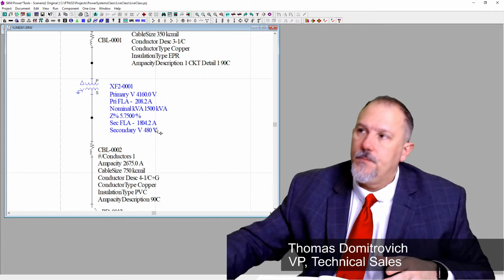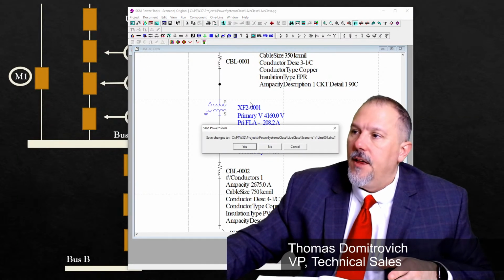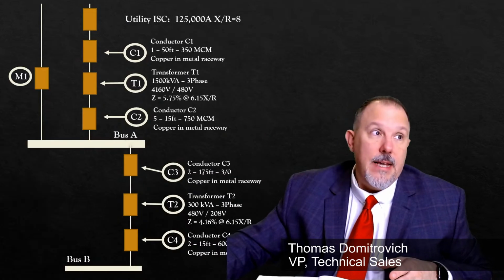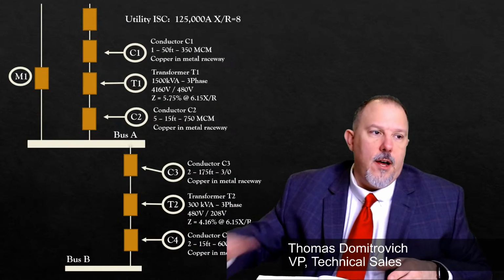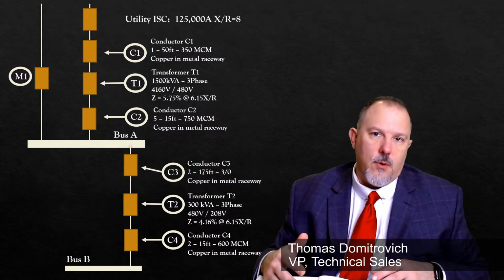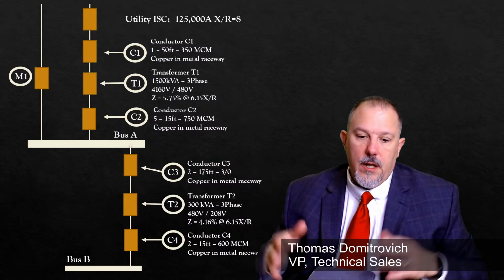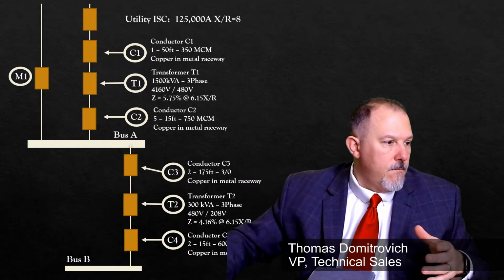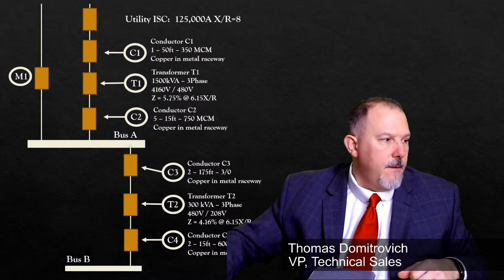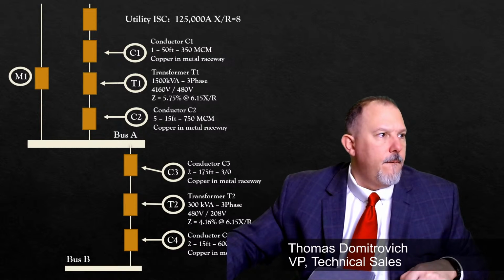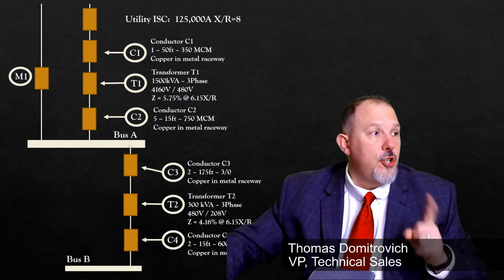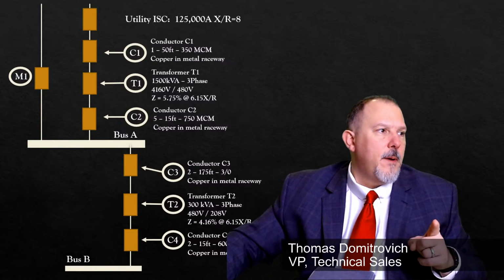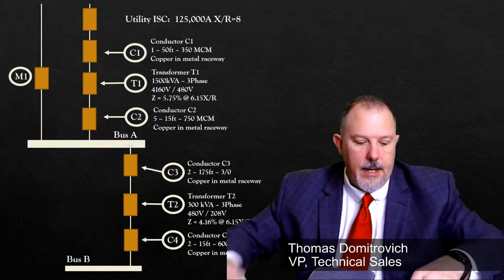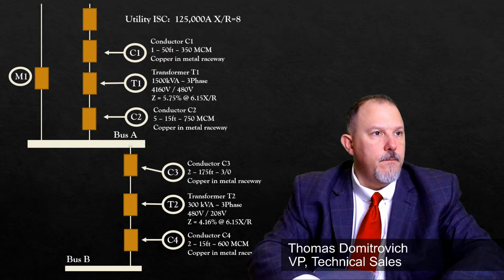Here's the thing that we do when it comes to motors. The rule of thumb is a lot of those motors are going to be smaller than 25 horsepower. So what we will do is, in fact, let me see if I have the IEEE color book. The buff book and the red book are two good documents, two good books. So I'm going to open up the red book first, and I'm going to look at motor contribution.